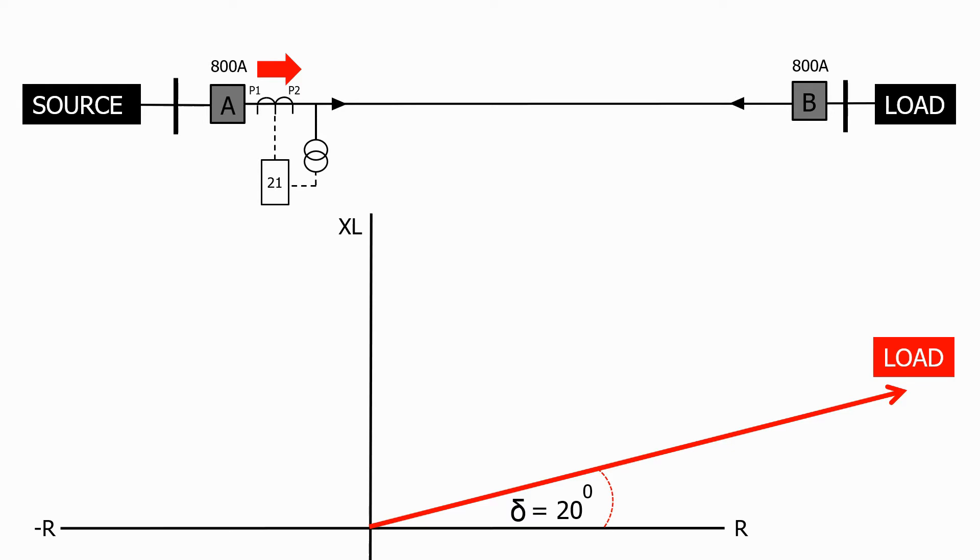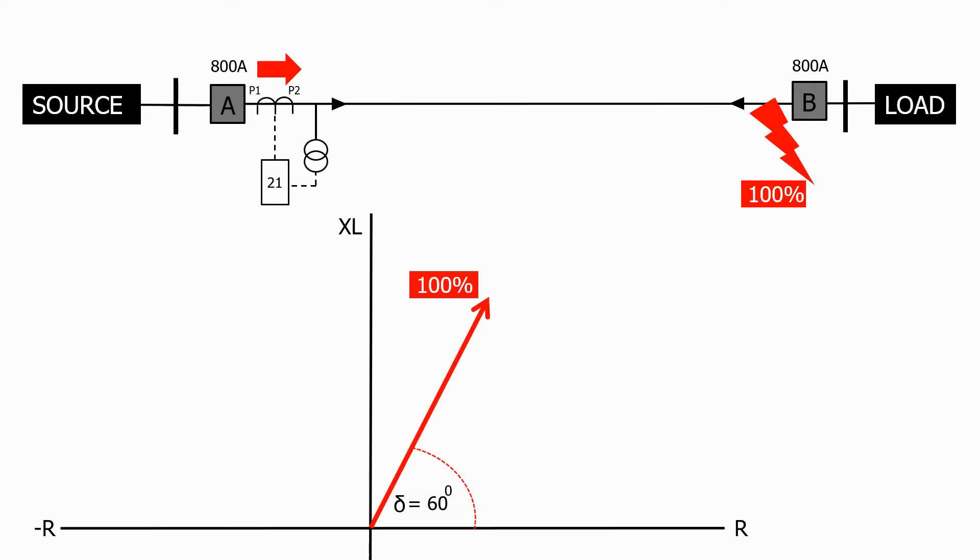If we get a fault at 100% of the line length, this is the impedance value that we will measure. This consists of two components, 100% of the line resistance and 100% of the line reactance. As the fault has occurred on the line, the characteristic angle of the fault impedance is normally about 60 degrees.